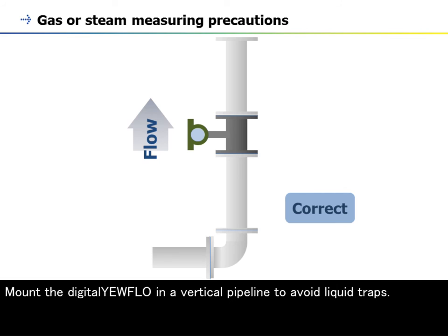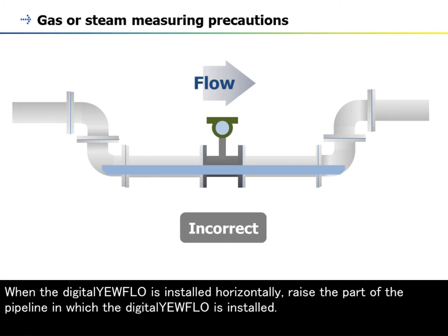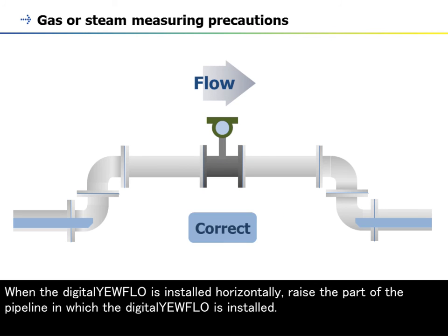Mount the digitalYEWFLO in a vertical pipeline to avoid liquid traps. When the digitalYEWFLO is installed horizontally, raise the part of the pipeline in which the digitalYEWFLO is installed.